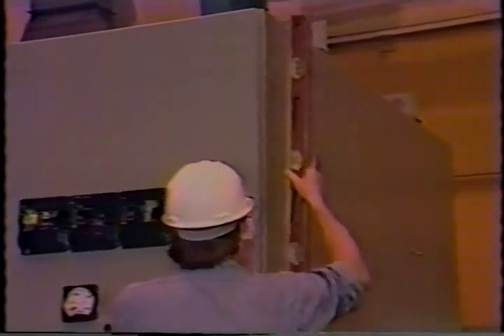Move each group into position, lining up the bolt holes in the base of the vertical sections with the bolt holes of the steel channels in the foundation. Check the installation with a level across the width and length. If necessary, shims may be used to level the assembly.